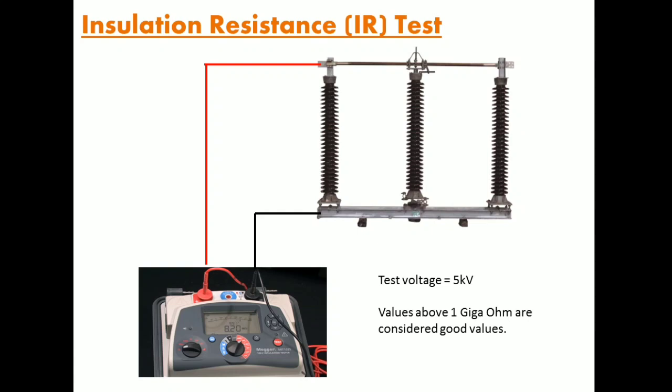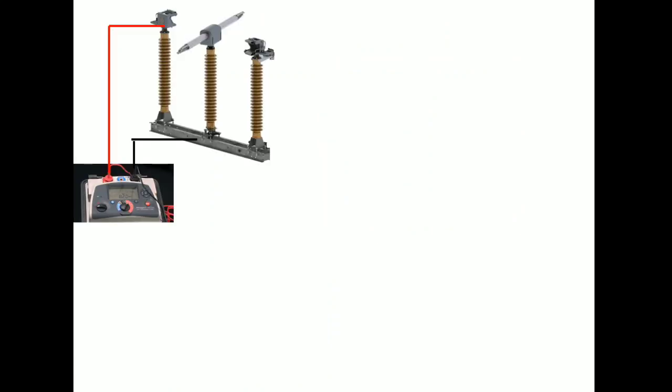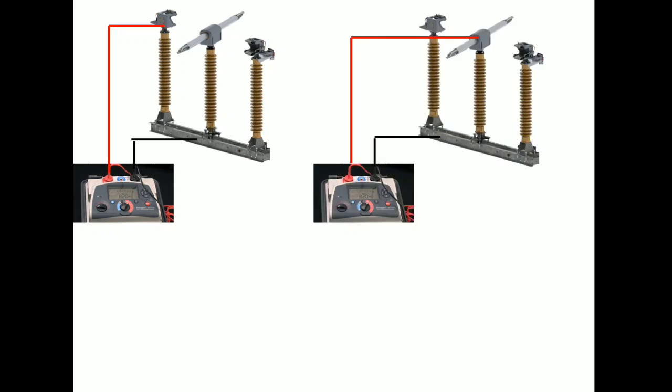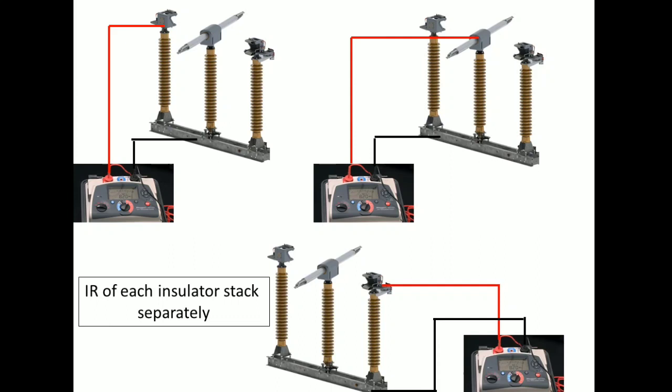Here we have taken IR of isolator in closed position. We can also take IR in open position by taking IR of individual insulator stacks. So these are the two tests that are conducted on isolators.